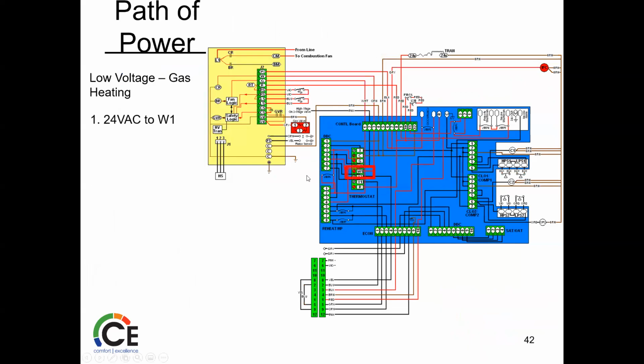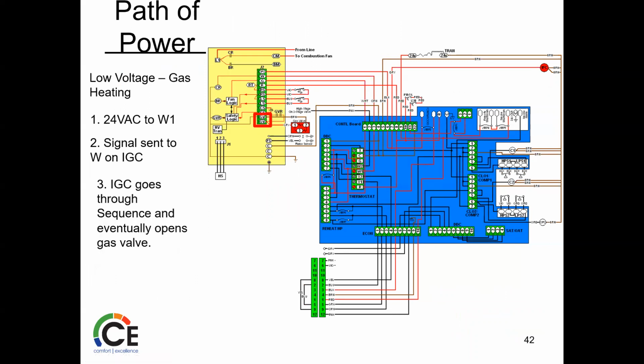Gas heating. Same thing, W1. Now at that point, it goes to the IGC, which is now, this takes control. Looks for gas valves. Says, yep, I got a W1 call. I need a gas valve. And then again, signal to IGC, it takes control of the indoor fan. So if you're trying to test this and you're trying to jump things out in heating, the sequence is different from what most residential guys are used to. So that's where some people get confused. Hey, I'm jumping G and I'm not getting a fan. It really depends on what unit you have, whether that will work or not.